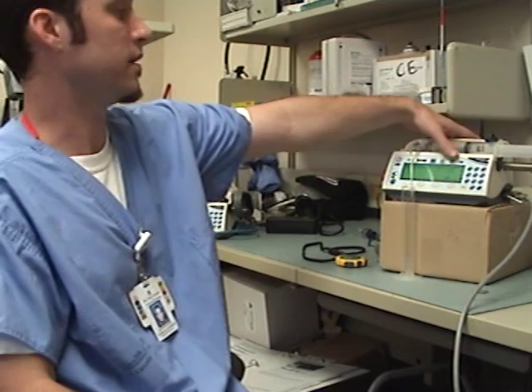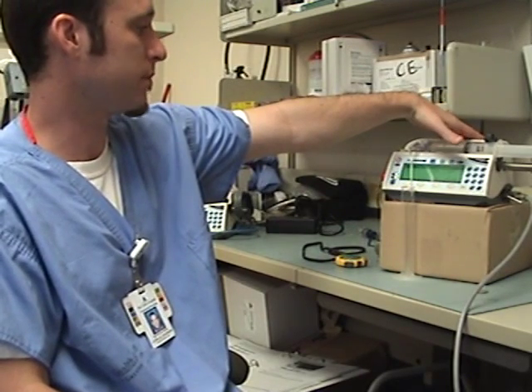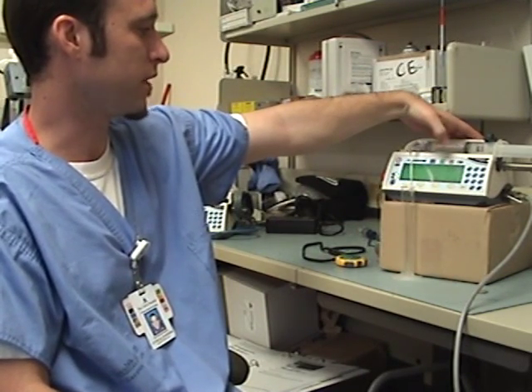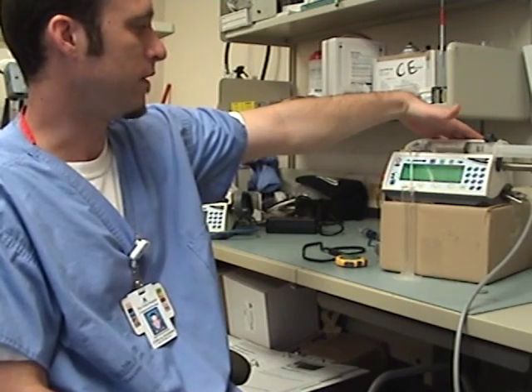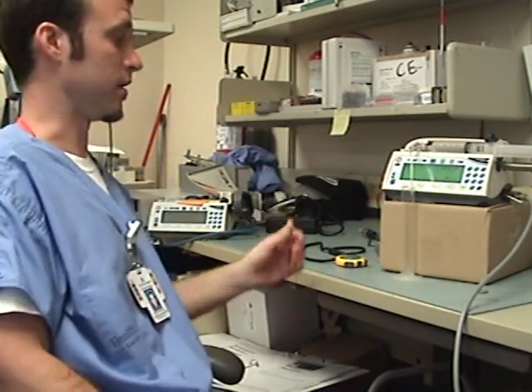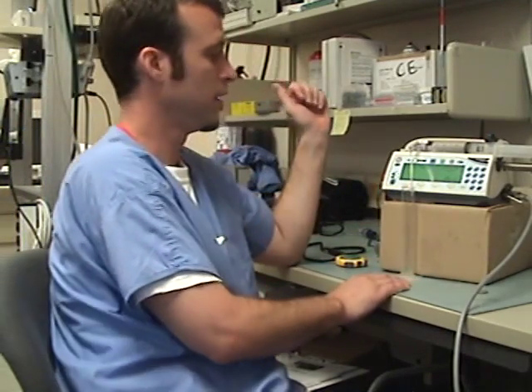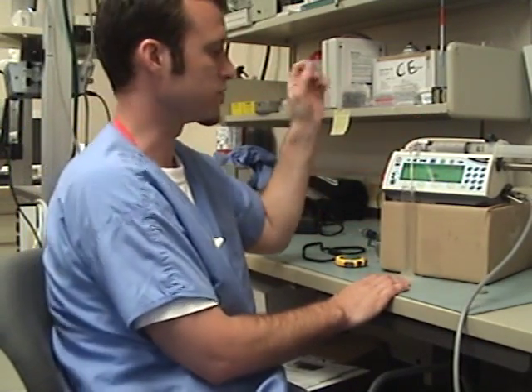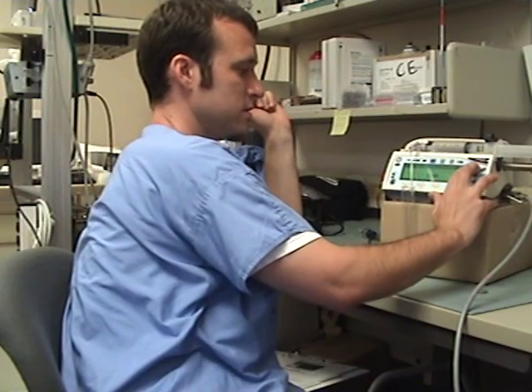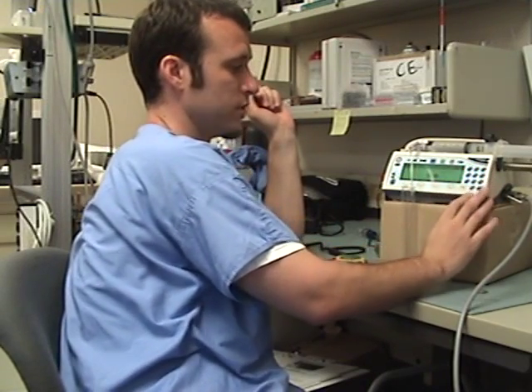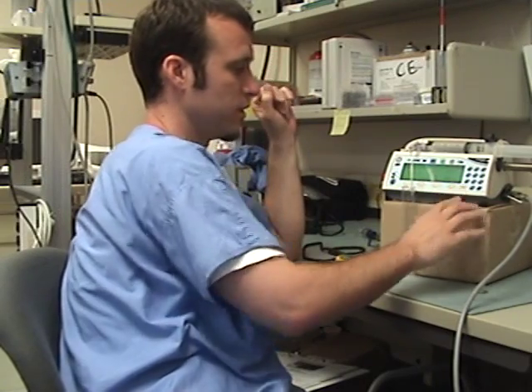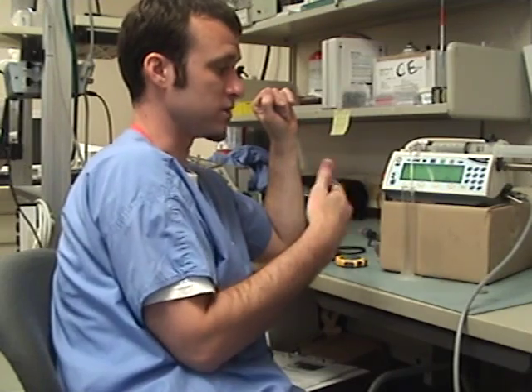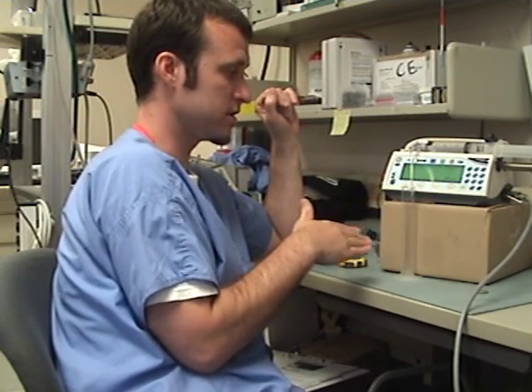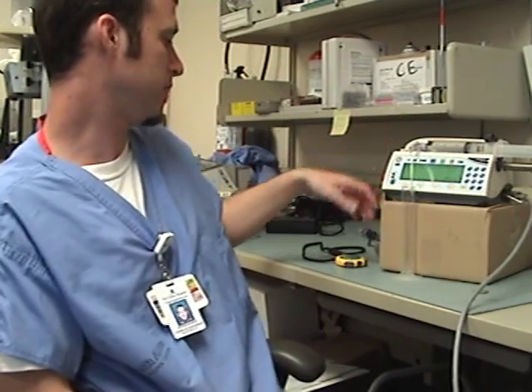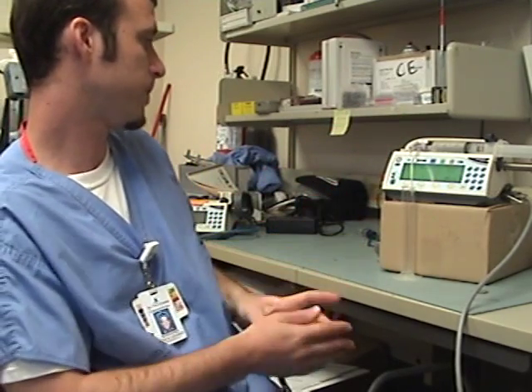This is the portion where I like to hit the stop button to verify that it's working properly, that it holds and keeps track of the actual proper delivered volume, and then press start again to ensure that it can run again if they need to make any changes during the case. You can also press change rate, which will now enable you to change the delivery rate while the pump is still running. So I can set it up to 120 and double the rate since I verified that the accuracy in terms of time for delivery is good at 60 milliliters. Now I can run it at 120 and verify that as well.